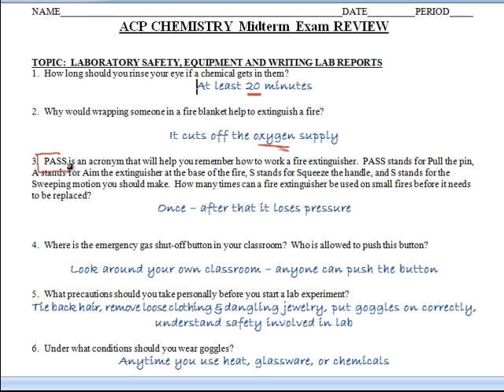You need to remember PASS when dealing with fire extinguishers. P stands for pull the pin. A stands for aim it at the base of the fire, not on the sides, at the base. S stands for squeeze the handle, and S stands for sweep. You need to go back and forth, back and forth at the base of the fire in order to put it out. You never want to shoot right in the middle, because if you do, this part of the fire is going to go that way, that part of the fire goes that way, and then you could end up with two fires instead of one. So PASS.